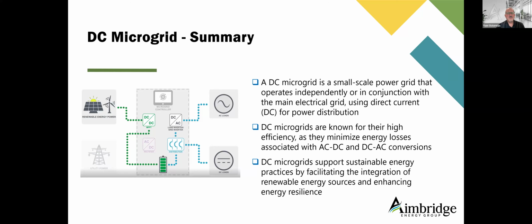The key difference is that we're trying to use DC power instead of AC. That's been facilitated over the last 30 to 40 years by dramatic advances in semiconductor technology, with efficiency increasing dramatically. So we can operate many load devices on DC, and in fact they're already operating on DC. If you have a wall wart style plug-in transformer or power supply fed from the AC wall socket, the output is feeding DC to that load. LED lighting over the last 20 years has been primarily low voltage in many residential and commercial applications, 24 volts DC or 48 volts DC.